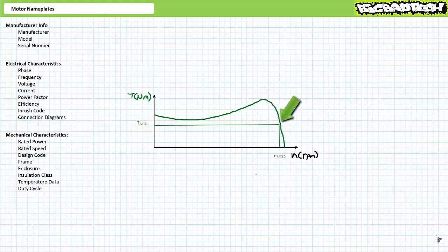This point is known as the rated condition. At the rated condition, the motor produces its rated mechanical power, rated torque, and rotates at its rated speed. The motor nameplate is a snapshot of those properties one might expect to observe at or around the rated condition. At the rated condition, a motor might be expected to draw the rated current at a specified power factor and operate with a specified efficiency.